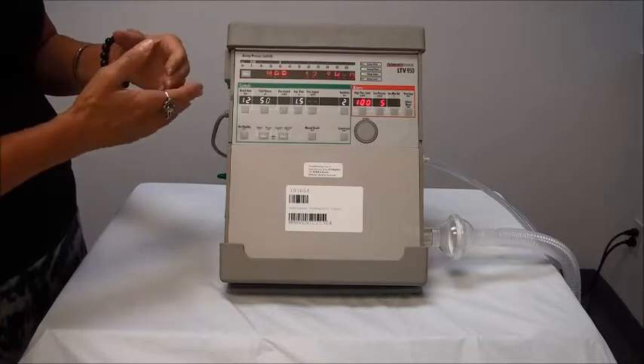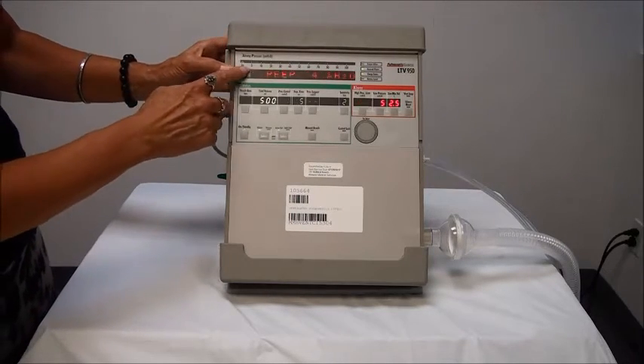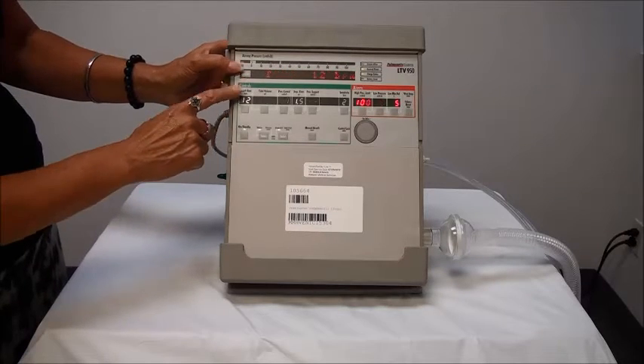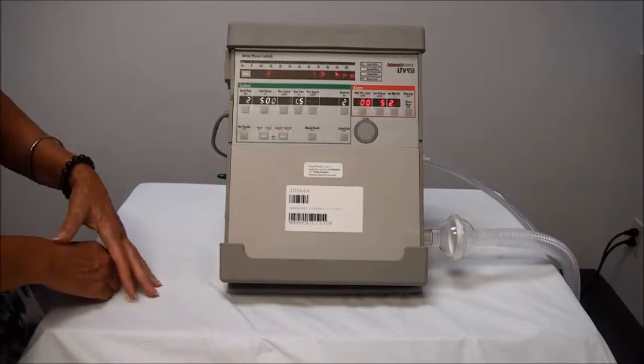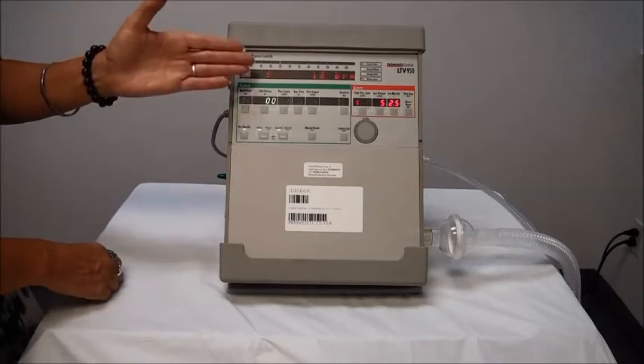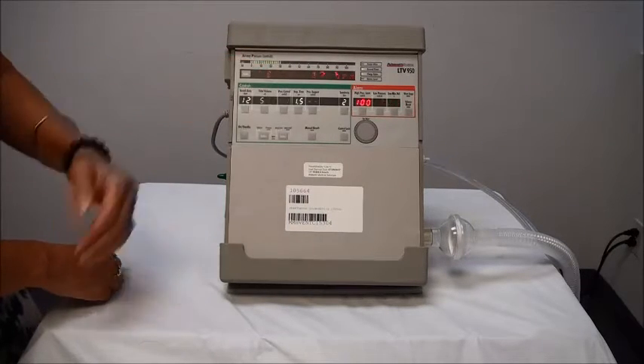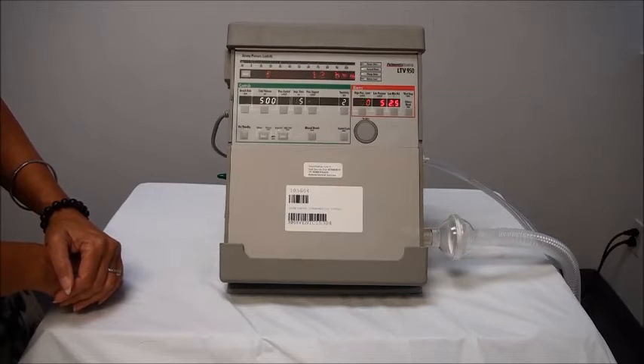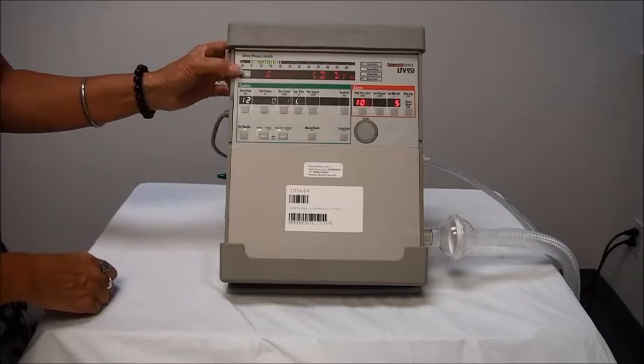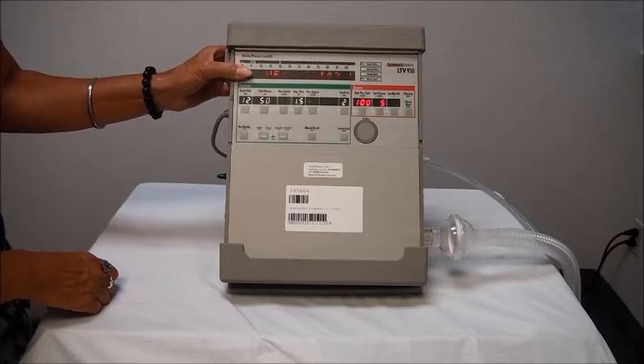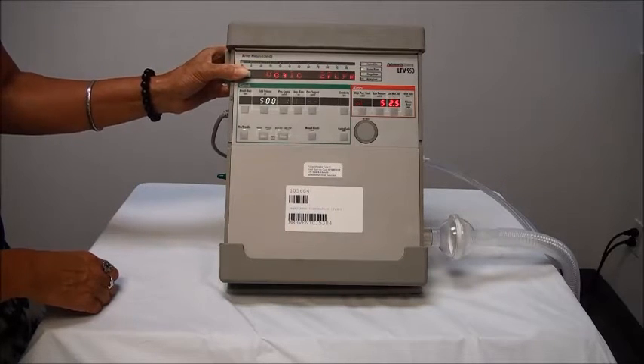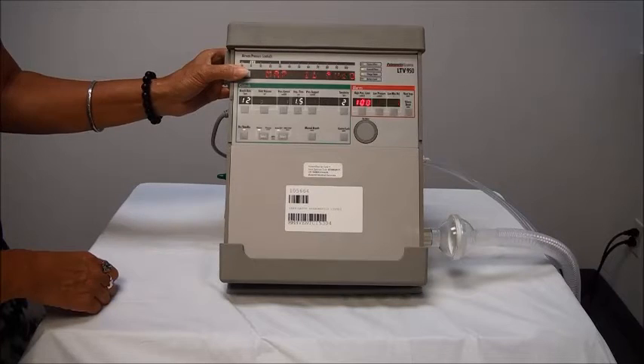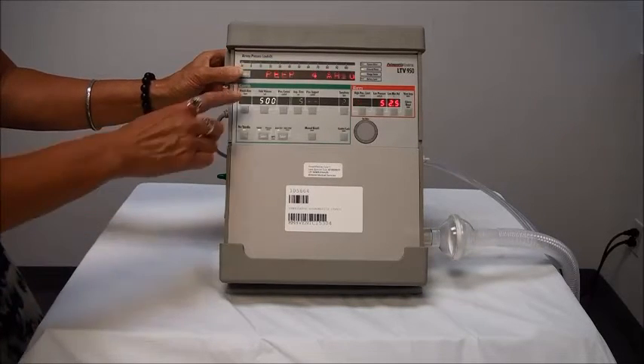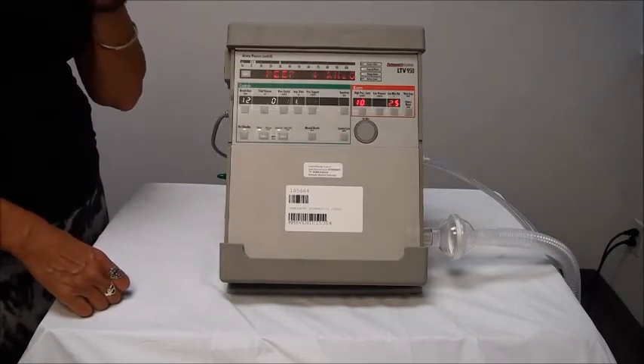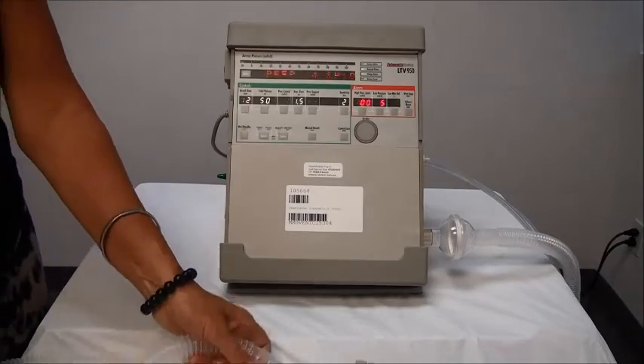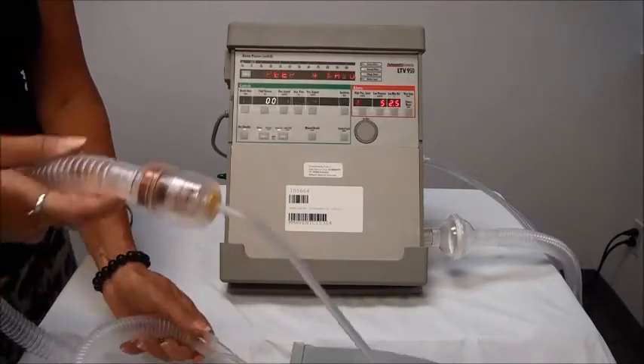Now if you want to stop it on one particular reading, there's a little button right here that says select. If I push that, it'll just stay. Right now it's on the frequency or breath rate, and it's staying on that setting. So if I needed to write that down or check something, I could. If I keep pushing the select button, it'll go through each one and tell me some different readings. Now I'm going to stop it right now on the PEEP setting because I'm going to show you how to set your PEEP on this particular ventilator.